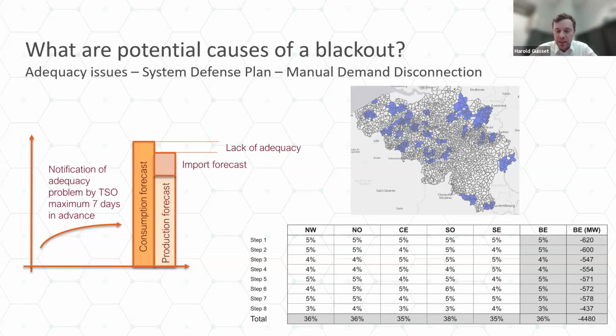And if during those analyses there would be a problem, a mismatch between consumption and production, there is a whole procedure with the governments, the National Crisis Center, and many different stakeholders, which is a procedure about scarcity. And in the event that we cannot solve this gap between consumption and production, then we might have to activate the manual load disconnection plan. And that would be something fully manual, as the name says. So it's not done based on a measure of the frequency, but it's really done based on what we see at the National Control Center, and it would cover the period where there's not enough production for the expected consumption.